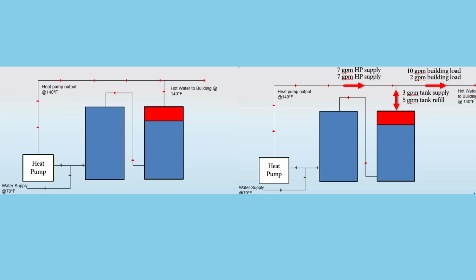This layering allows the system to operate efficiently with a large temperature lift. If warm return water mixes in and destratifies the tank, efficiency drops sharply. That's why maintaining stratification is a core part of system design.